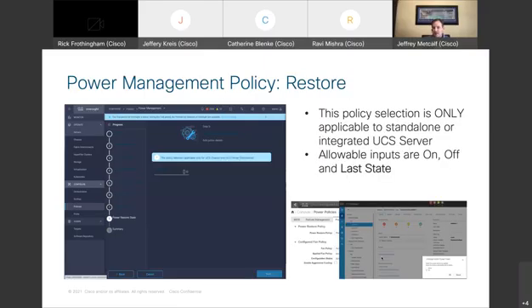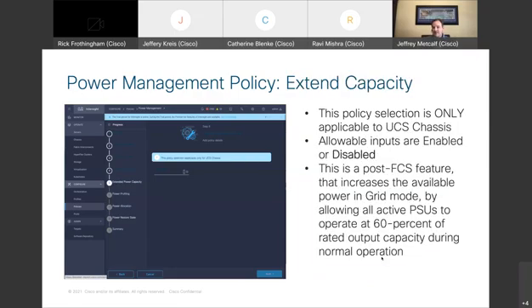The next thing I want to highlight is extended capacity, for environments operating in grid mode. With 6 power supplies—and the reason we moved to 6 is that as we get to higher density components, customers are bringing 3-phase power to their rack products, using 3-phase rack PDUs. The PDU strips off one phase and provides single phase to each power supply, so the power supplies themselves are single phase. To balance the load across each phase, you need multiples of 3, hence we moved from 4 power supplies to 6 to improve load balancing.